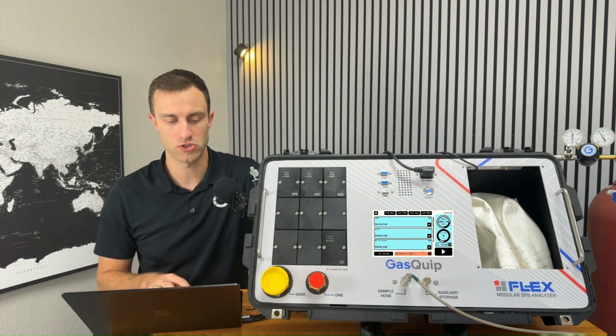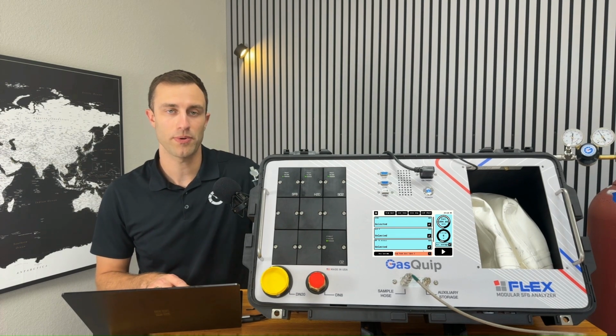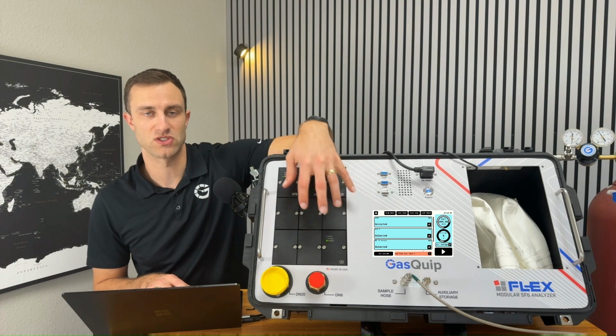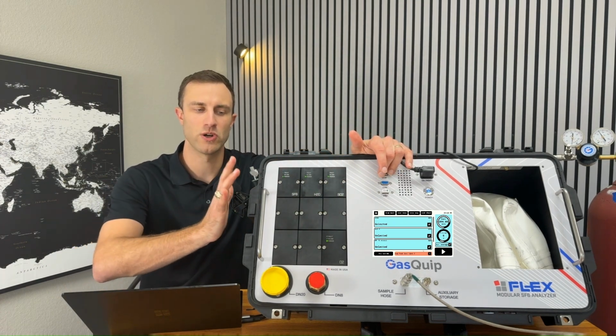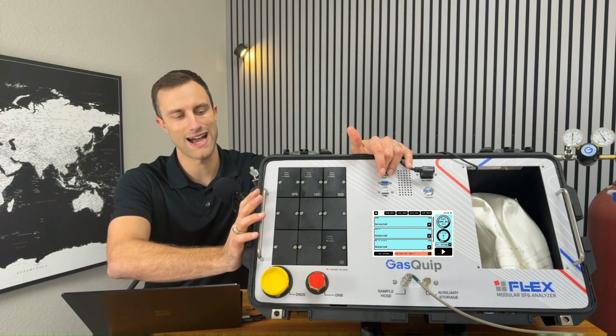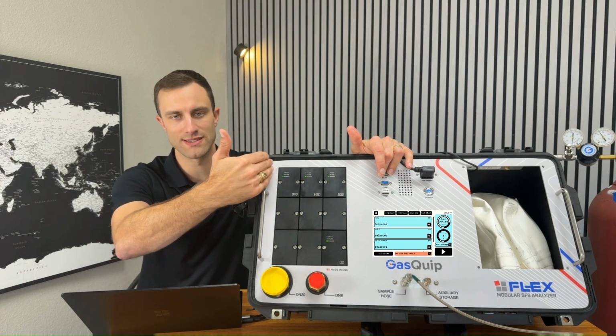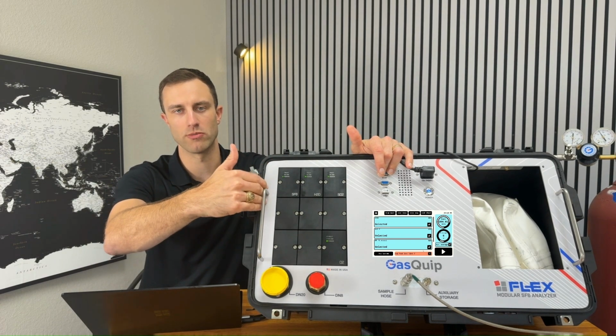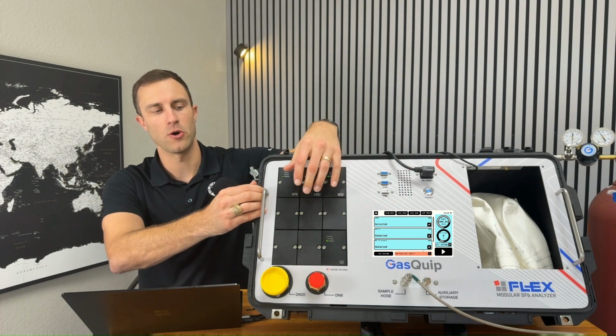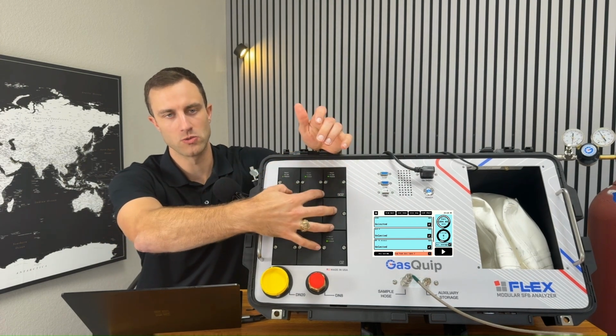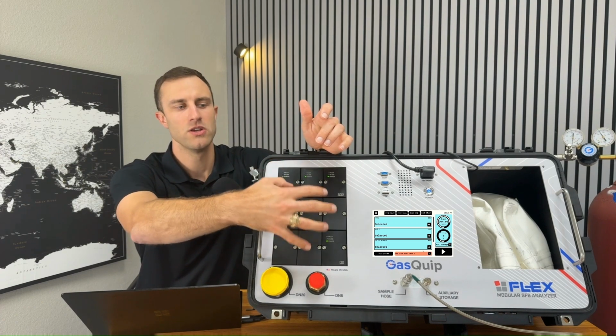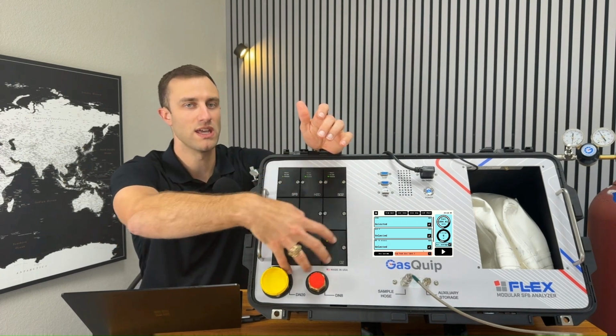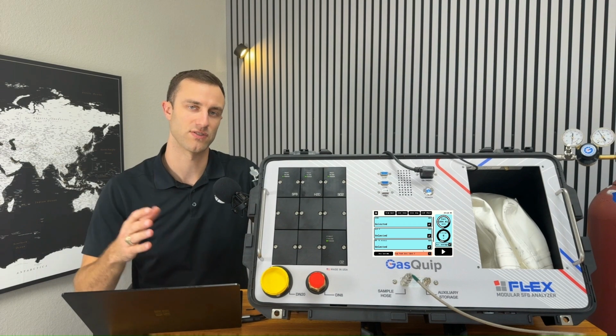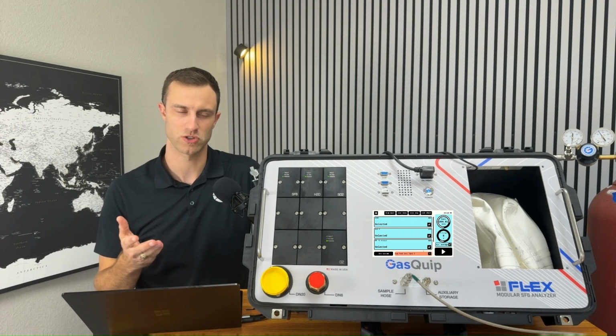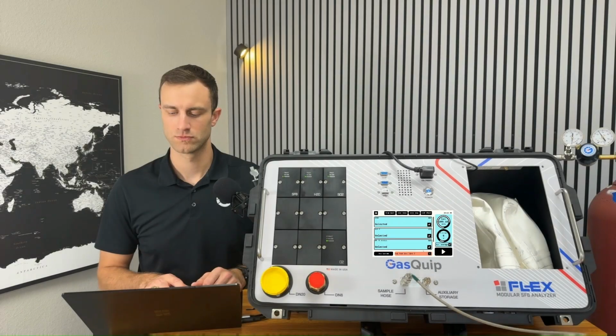The sixth way that I would try to troubleshoot stuff like this is to swap your modules into a different slot. It could be a situation where someone dropped the unit on its side and there are sensitive solenoids that sit alongside this module manifold that could have been damaged. So each individual module slot has its own solenoid. You can swap those modules into any of the 9 module slots to test if it's working better on one over the other, which could be because of damage.